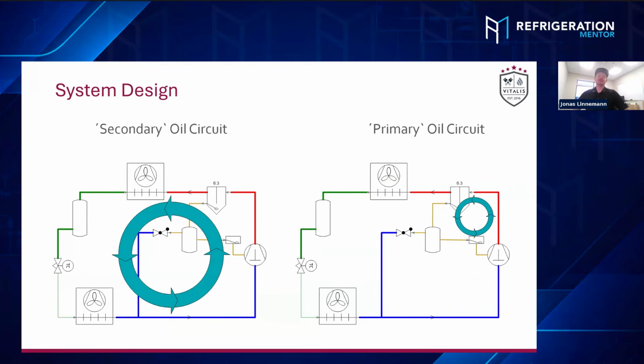Let's have a look at the system design itself. So these are pretty simplified system PIDs, I would say, and there are basically two different oil circuits. The one is the primary oil circuit, which is where the oil belongs: the compressor, oil separator, and the oil reservoir. And then there's the secondary oil circuit, which is as soon as the oil travels out into the system, to the gas cooler, into the supermarket, the cold storage rooms, the evaporators.